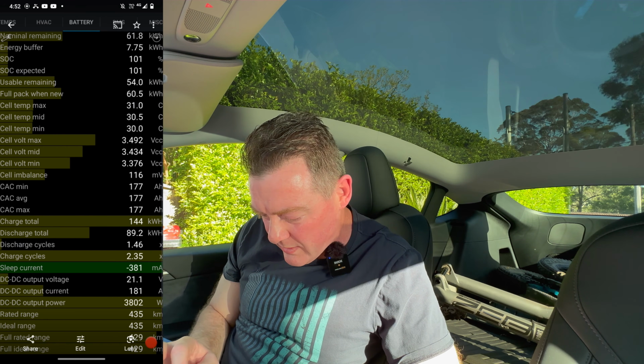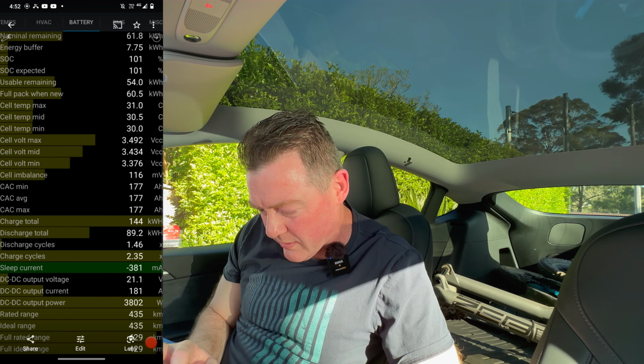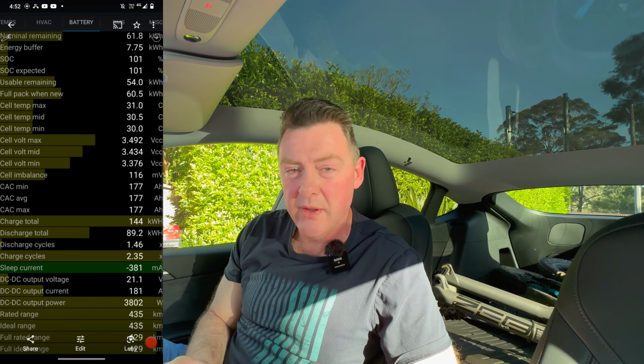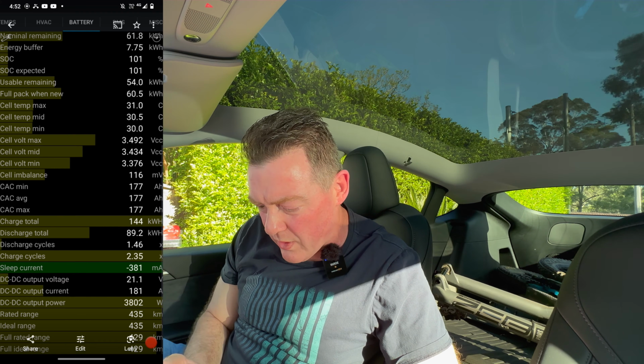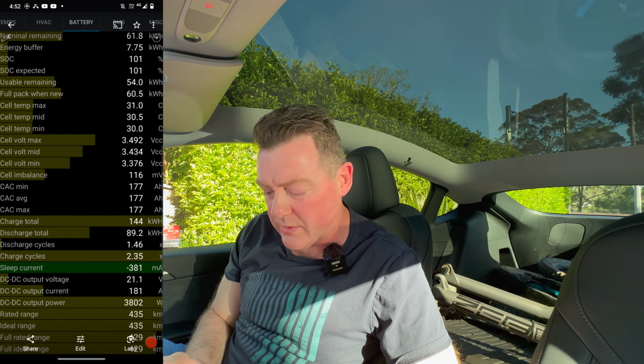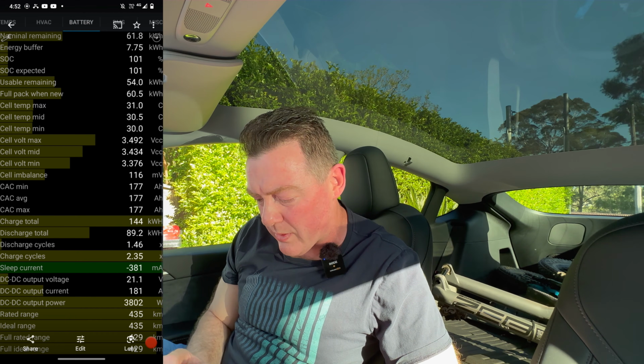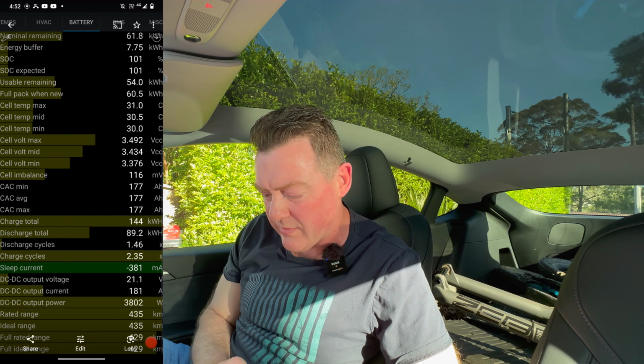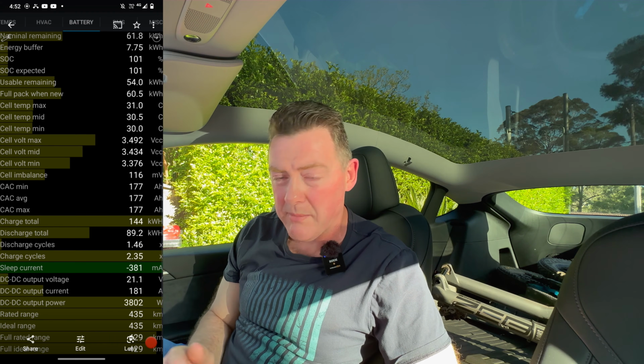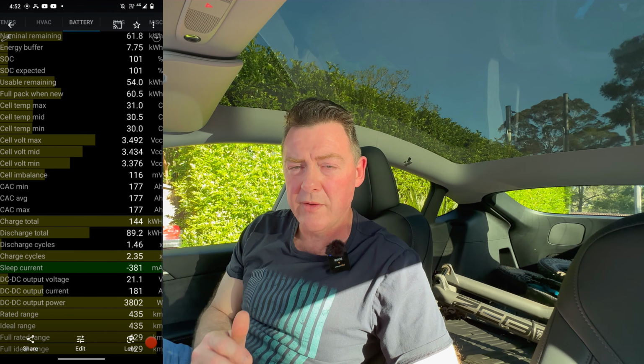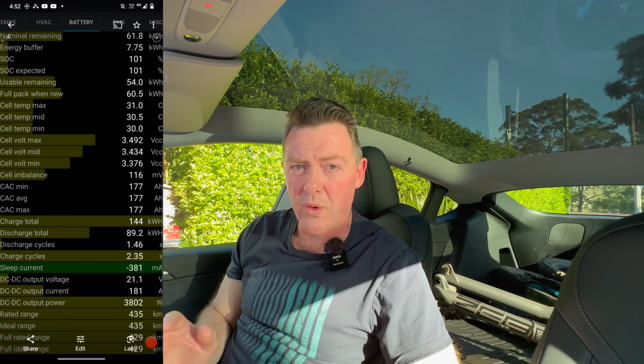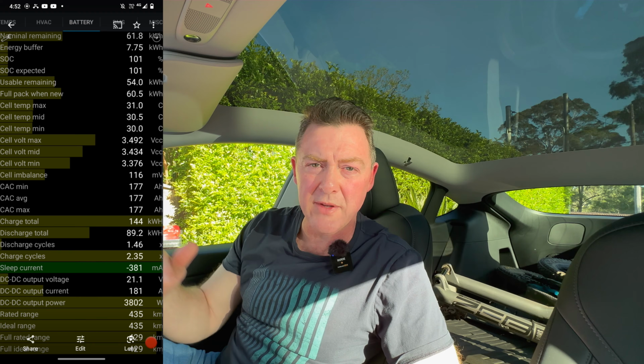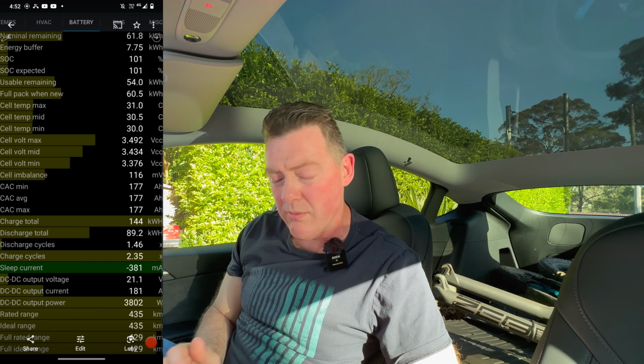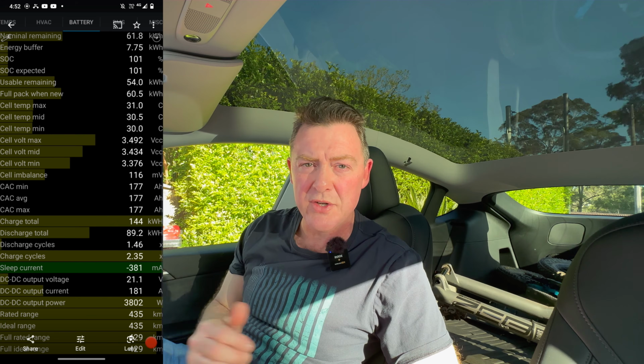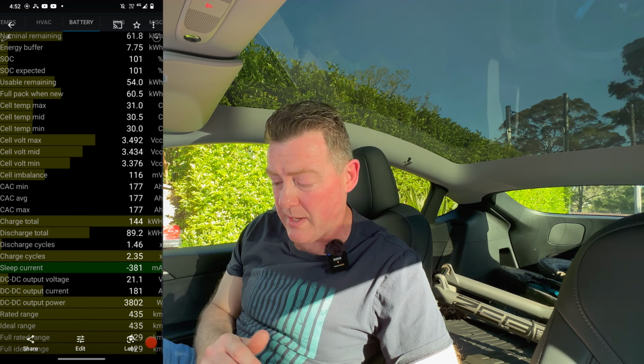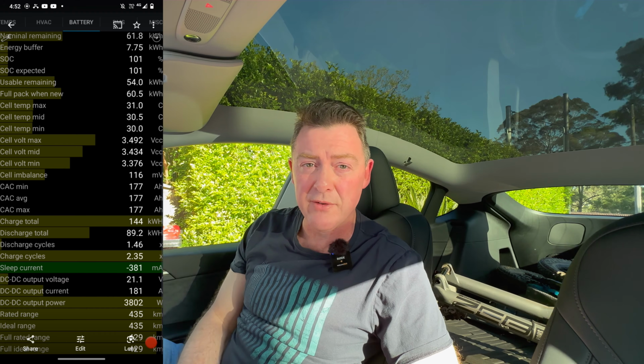Now, what I didn't point out in that other one was here - this is where the cell imbalance got quite bad. You can see 3.49 was the cell with the highest voltage, and the cell with the lowest voltage was 3.37. So there's a big difference there, 116 millivolts. That may not seem like much, but that's a fair bit of imbalance across this. The imbalance normally sits at 4 or 6 millivolts most of the time. Sometimes you might see it go up to 10 or 15, but that's pretty rare - that's probably after you've done a lot of fast charging. You'll see the imbalance come up a little bit, but as you do some slower charging, you'll see that come back down to 4 millivolts.